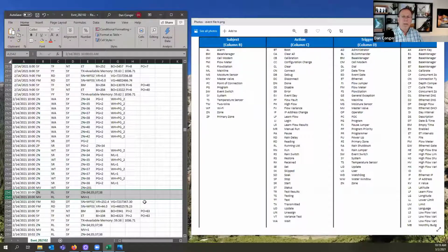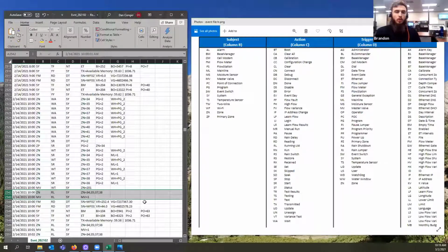Oh, yeah. Okay. So now if a zone didn't run, would we have two places to get that information? If a zone couldn't run because there was an electrical issue, pardon me, would that show up in this file? It won't. No. If there's an alarm, it'll show up in the normal places. We used to have alarms built into the event file, but we've since separated them. So in the same admin manager location, you can pull an alarms file that also shows any historical alarms, even if they've been cleared, for the date range you select.